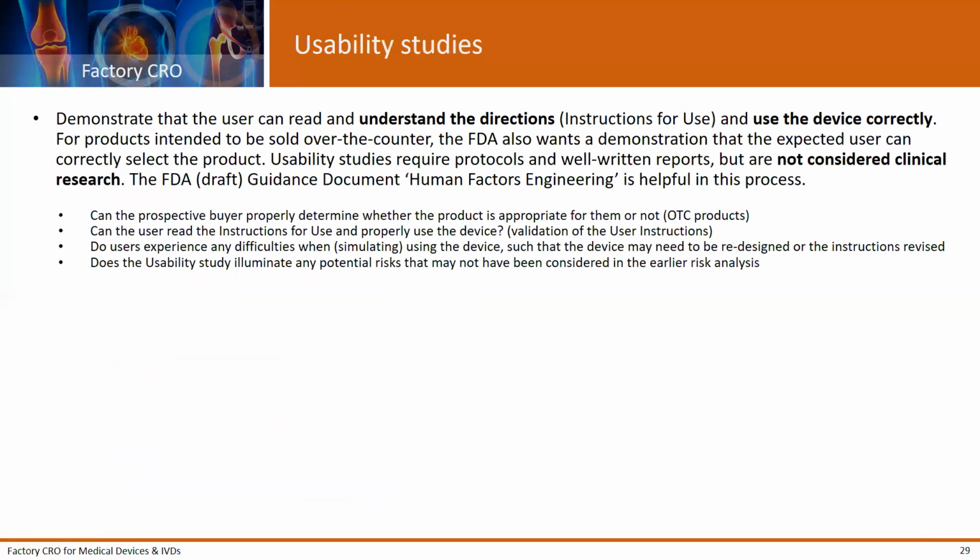Usability studies basically demonstrate that the user can read and understand the directions, the instructions for use, and use the device correctly. Those studies require protocols and well-written reports, but they are not considered clinical research. There is a guidance document, which is very helpful. Basically, user testing boils down to the following 4 questions.